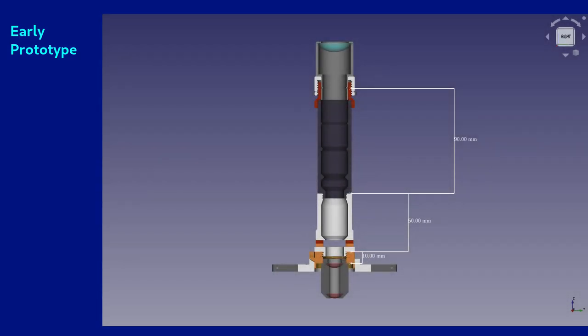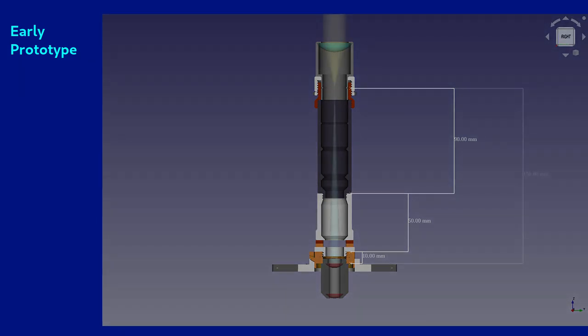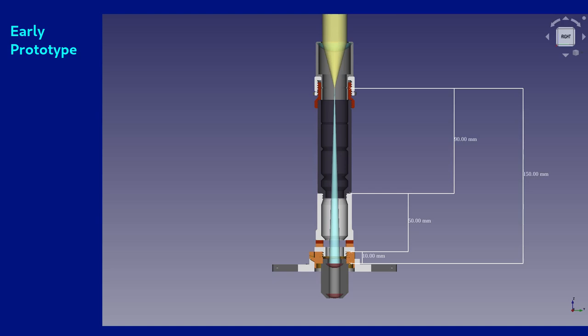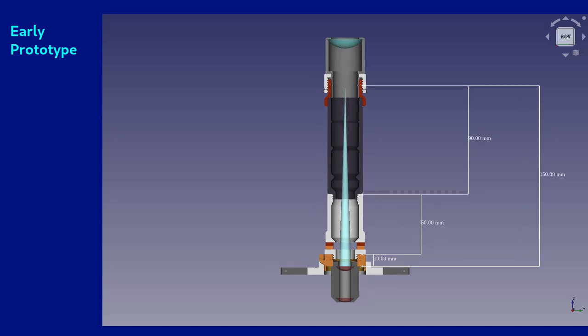I therefore designed all the ocular head options on the basis that there was a further 90mm of optical path length left to fill before the focal plane of the ocular, which must occur at 150mm from the flange of the objective for compliance with the RMS standards, as was described in the video on beam splitters and the advanced filter block.